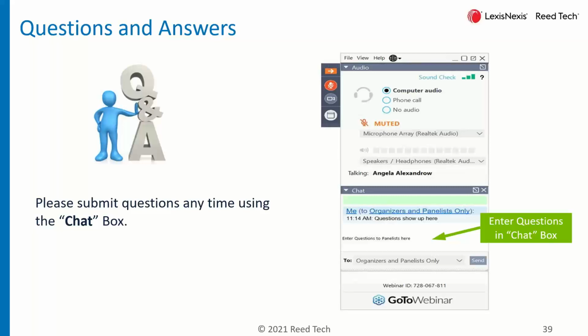Here's one about a very specific scenario. If you have a collection device that can be attached to a Class II device, but does not need to contact skin, an example would be a collection bag for a catheter, would that still be a Class I? Yeah. So used with a Class II, we start to get into systems or convenience kits, as the FDA refers to them, where you have multiple medical devices that are packaged and distributed together.